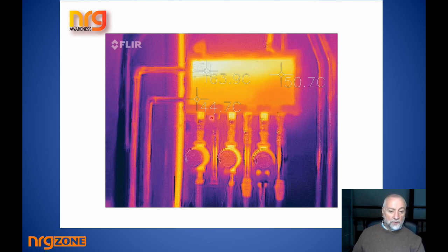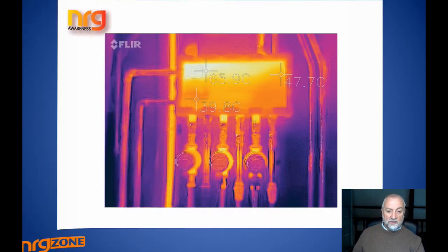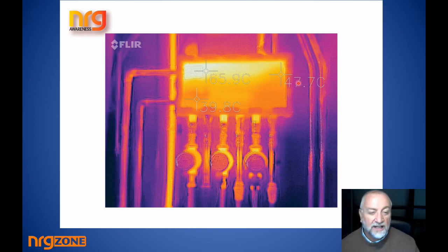So if we go to the second now, you can see that there's a temperature coming here, 63.9. There's about 50 degrees at the bypass, and we're down to 44 here because some of the cold is being recirculated. But then when we rectify the problem by sorting the pumps, the bypass temperature might stay around 47ish, that's fine. 65 on the flow, but now look at this lovely 39 degrees, so we've got a very good 25-degree drop across the system as it's heating.